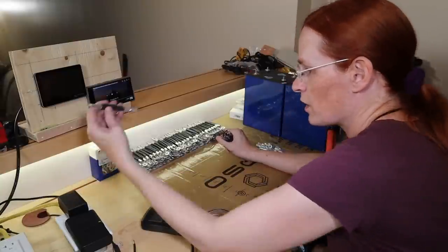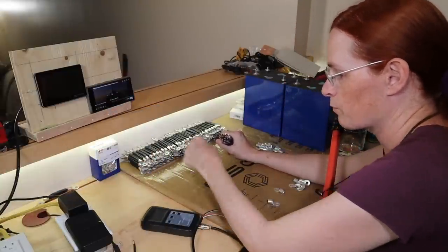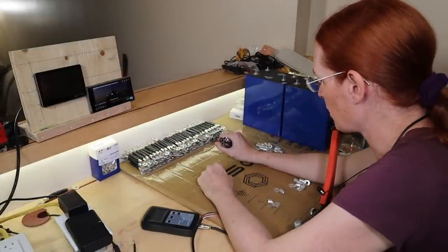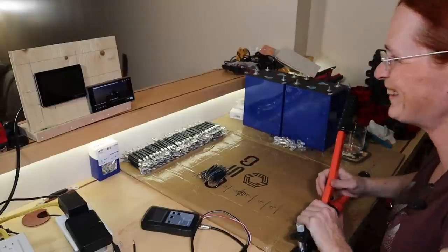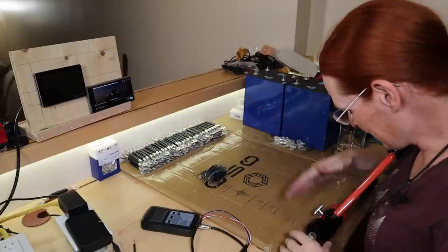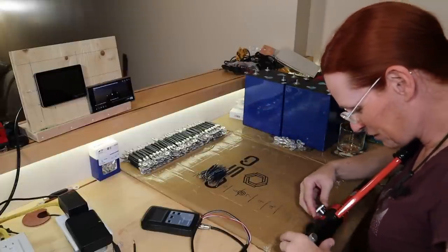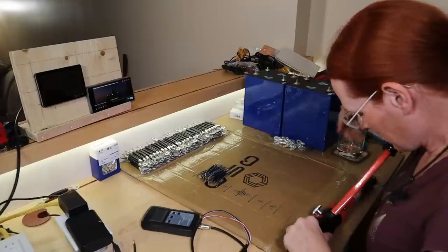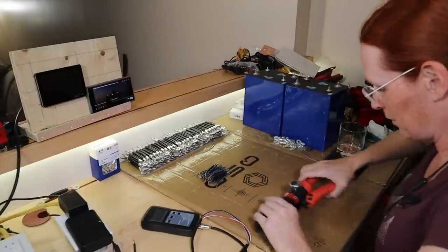I'm going to find my heat gun and start cutting up some shrink tubing and shrinking all these. All 90 of them measured at 0.11 micro ohm of resistance. Every single one of them, with the exception of this one, which is 0.14. But that's why it's going in the discard pile. You did, girl. You did good little hydraulic crimper. You didn't die on me.